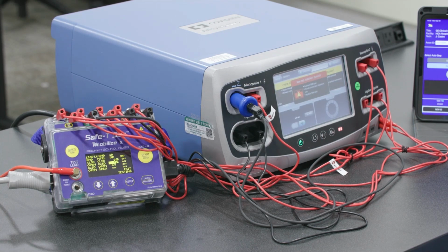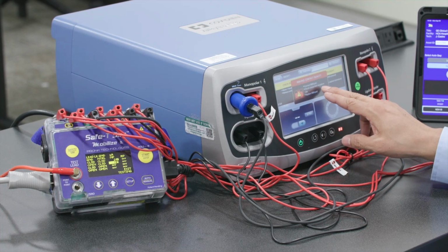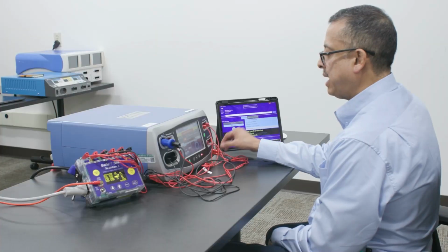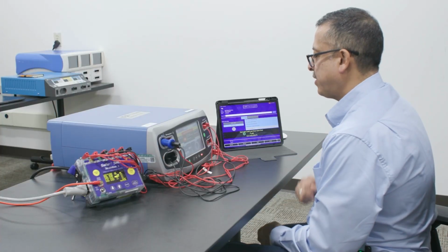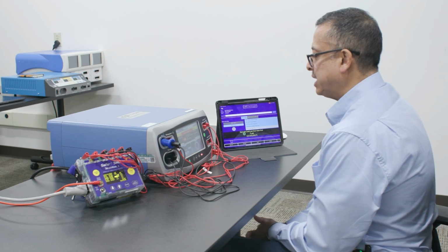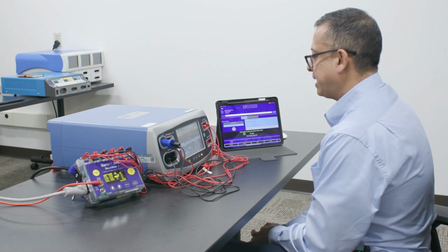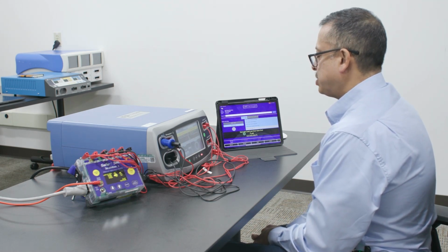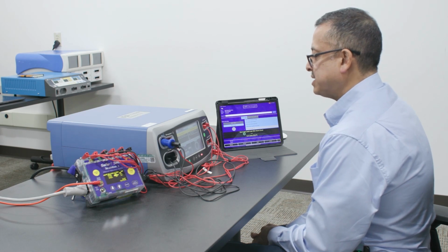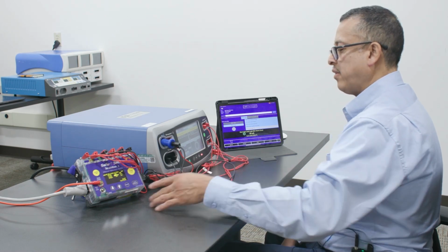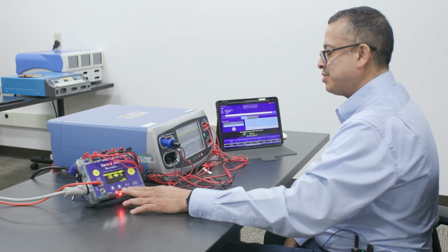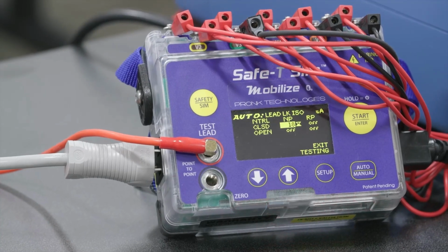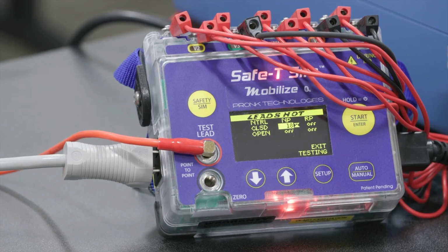So you see here, you may see a REM contact quality error here, and that's because we do have the REM line shorted to the safety analyzer. That's normal. It won't affect your leakage measurements, so that's not going to impact the measurements at all. Just let it continue through the safety test as it's going through it. You can see here you have the warning letting you know the leads are hot, so just a reminder not to touch the leads. And it's just going to go ahead and perform all of those tests that we need to.